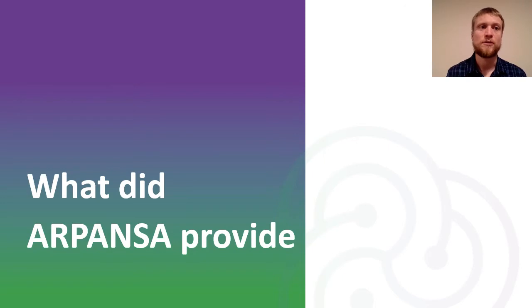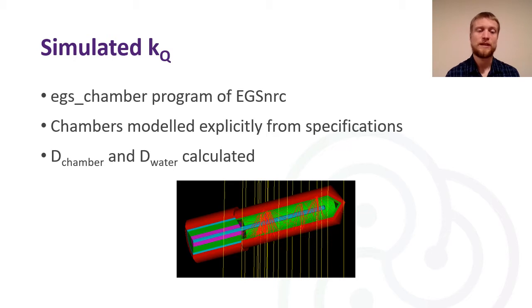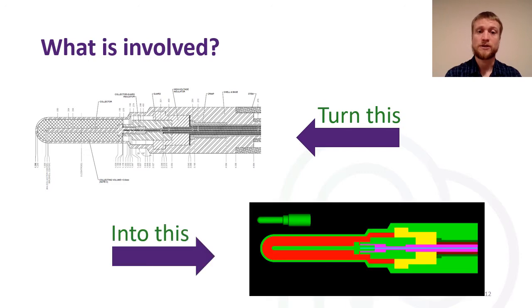ARPANSA contributed multiple simulated KQ data points, all simulated with the egs_chamber program of EGSnrc. All chambers are modelled explicitly from manufacturers' blueprints and specifications. In each case, for each chamber and energy, we modelled the dose to the chamber and dose to a water volume. This involves taking the manufacturer's specifications or blueprints — very detailed drawings — and turning them into an equally detailed Monte Carlo model, so that we can use that in simulations to get the most accurate possible understanding of radiation propagation and dose deposition in the ionization chambers.